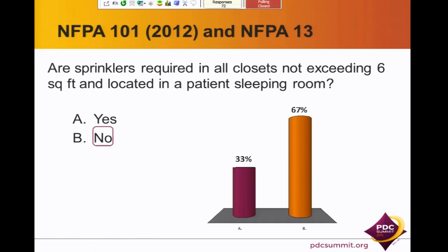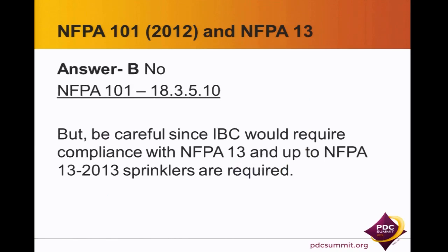The correct answer is no. But be careful with this one. The 2012 edition of the Life Safety Code says no. We've taken exception to NFPA 13. It's the 2013 edition of NFPA 13 that has been modified to say sprinklers are not required in certain closets in patient sleeping rooms. If you have to comply with the IBC, you are probably referring to a different edition of NFPA 13. So the answer might have to be just the opposite, if your building code official requires you to meet that earlier edition of NFPA 13.